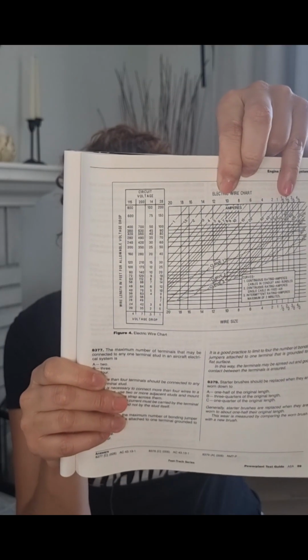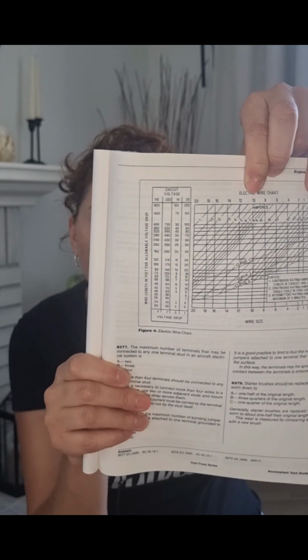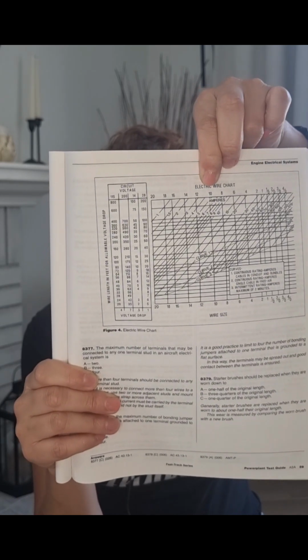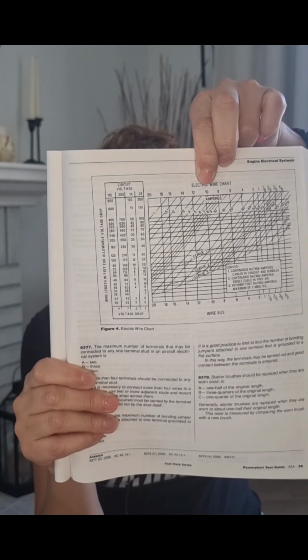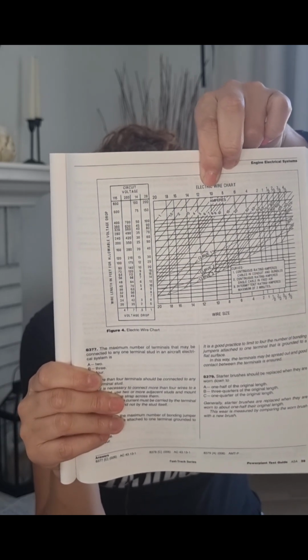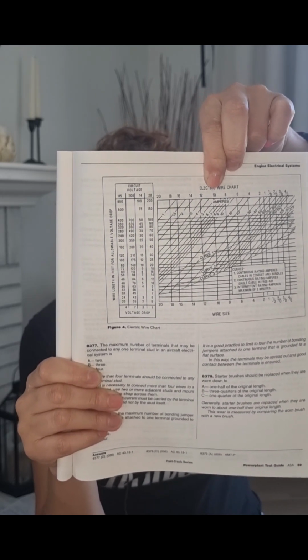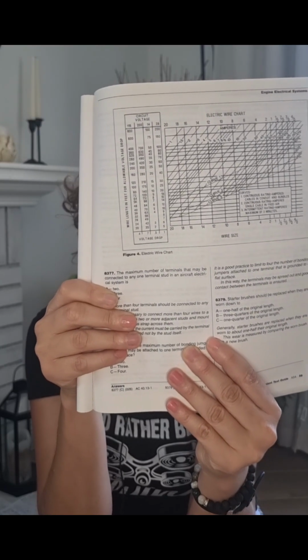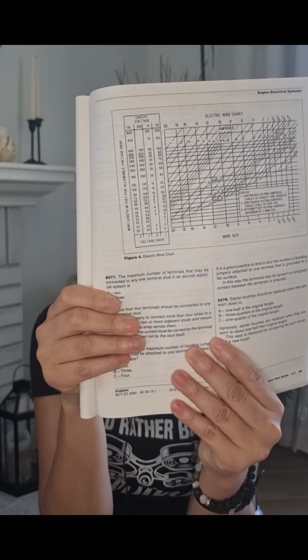What you do is you draw a diagonal line downward and to the left parallel to the 10 amp line, 1/5 of the way between the 10 amp and 15 amp diagonal. Draw a line horizontally to the right from the 45-foot mark in the right-hand column. These two lines intersect between the vertical lines for a 10 gauge and a 12 gauge wire, always select the larger wire.